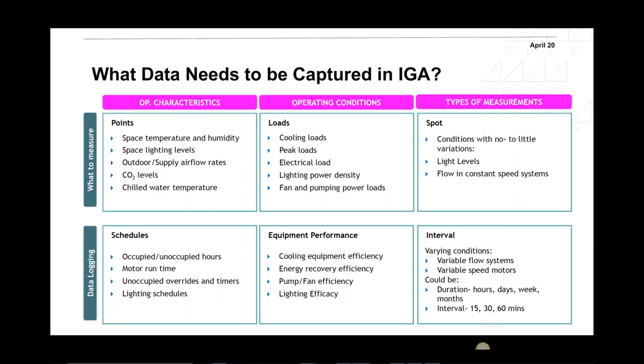Space lighting levels: sometimes you go into a building and find it's too bright. You take the measurements, lux levels, and might find out it's 1000 lux in a corridor. You can easily do de-lamping in that case, removing some lamps to decrease the lighting levels to what is required. For offices, it's normally around 300 to 500 lux as per the standards. You need to take CO2 levels sometimes to see if the building is under- or over-ventilated. So I would take outdoor airflow rates, CO2 levels, and VOC levels if I have the equipment. Chilled water temperature, supply and return, to see if they have any low delta T issues. Operating conditions like loads, cooling loads.